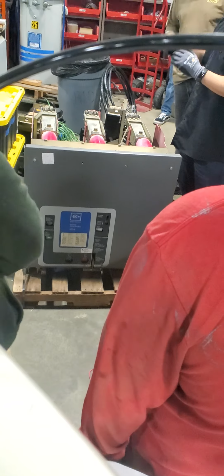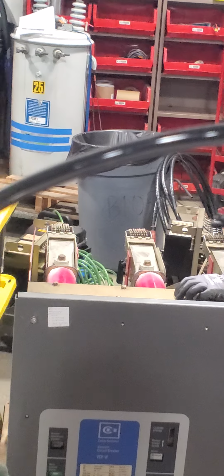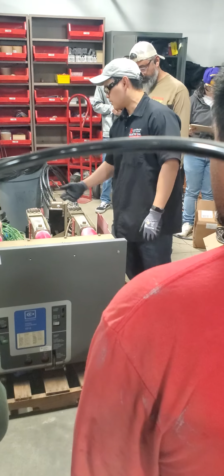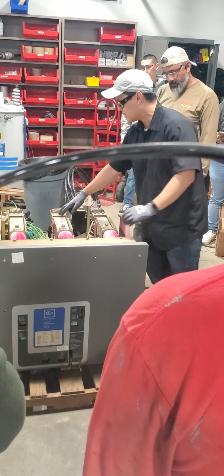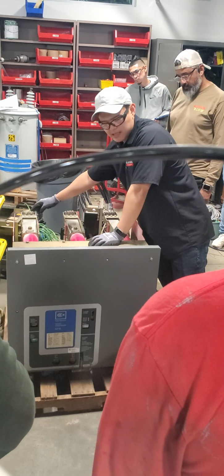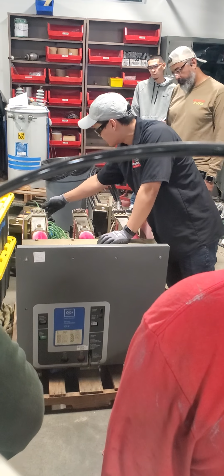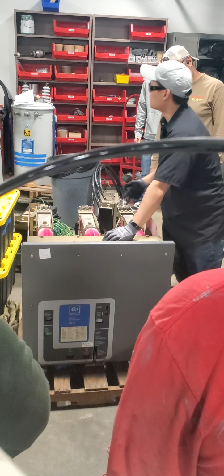Question - since this is high voltage, is it okay to clamp on the contact fingers? It shouldn't be. Exactly, that's an excellent question. We know these contact fingers are pretty loose, and if you recall when we performed the contact resistance DLRO ductor test, this is a very poor connection - you're relying on luck at that point to get the 50% rule because the connections are so unreliable and unrepeatable. So that's why we'd get onto the main stabs or even on here. But you're exactly right - because it's high voltage, to the tune of 28.8 kV, we're not too worried about it making that jump. Great question.